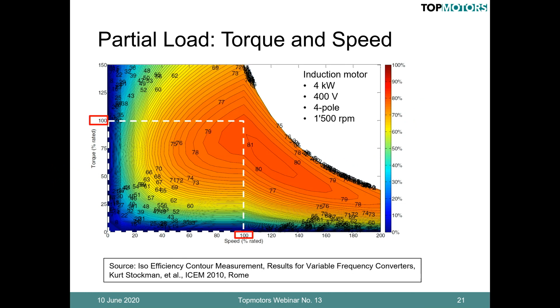What does that mean? That means the nominal sizing of a motor and a frequency drive to this 100% torque and 100% speed is fine. But when you look at a machine, typically a fan or a compressor or a pump, you might want to go to a zone in this efficiency band that comes more closely to the actual operation. And this already touches on the problem. If the motor feels very well and is well within its rated performance square, that doesn't mean that the pump or the fan or the compressor it drives is also at its optimum performance point.